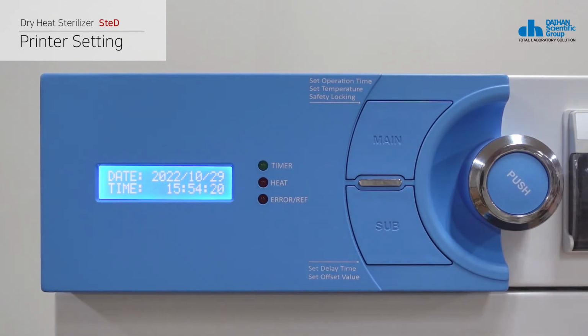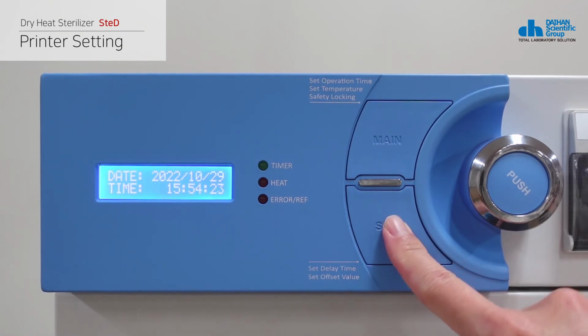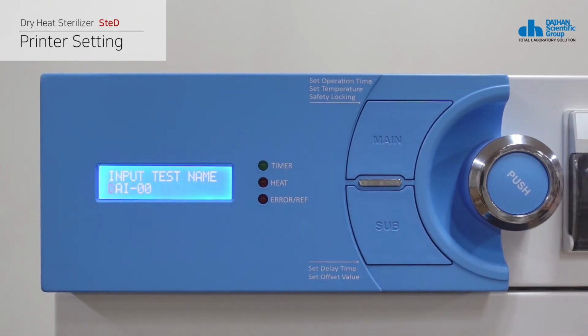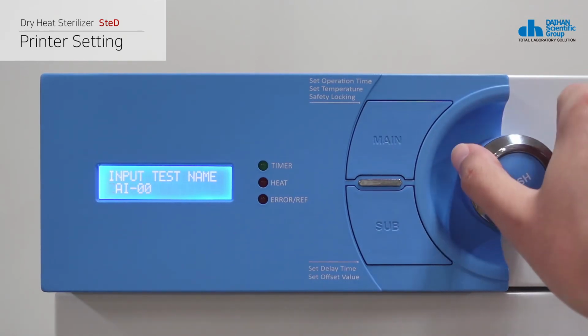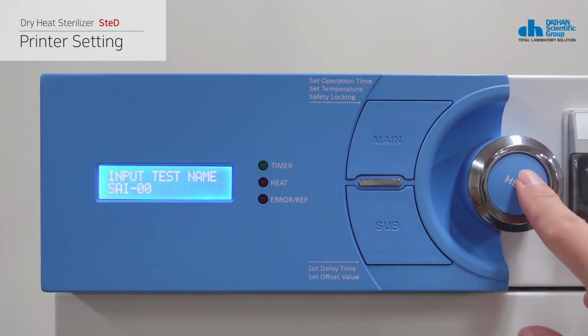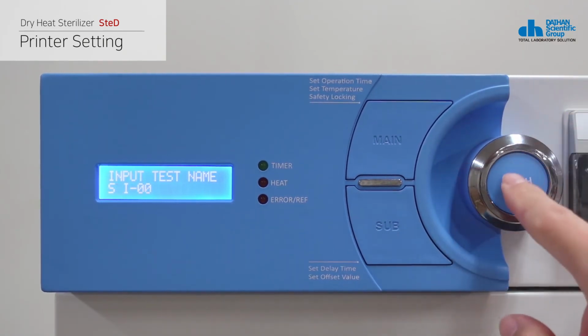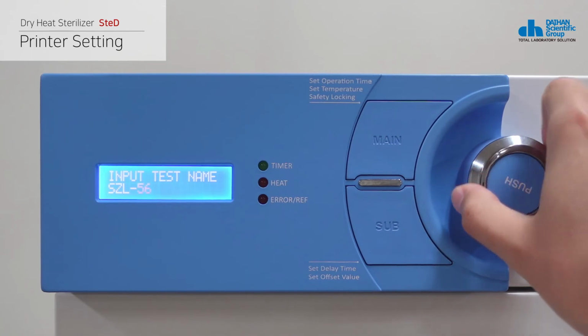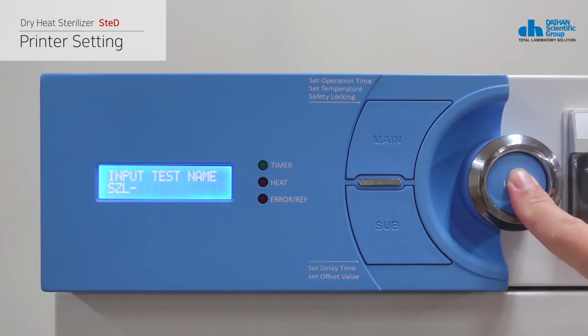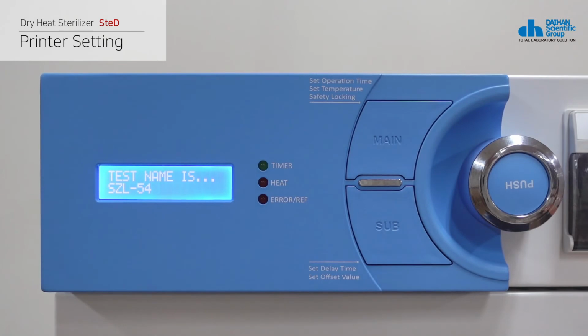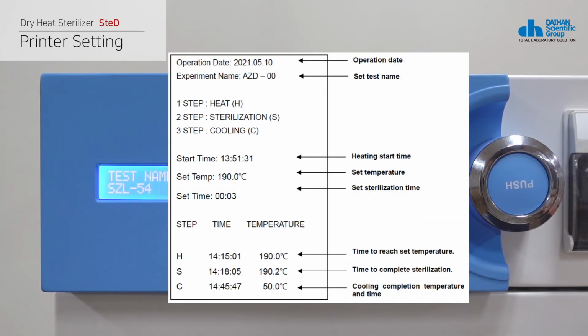Press the sub button on the current time setting screen to switch to the screen where you can set the sterilization test name. Pressing the push button moves the cursor that can be set, and turning the knob sets the value. When you press and hold the push button after the setup is complete, the screen flashes and saves the setup. As sterilization proceeds during product operation, the set date, time, and test name are printed out. The temperature and time information are printed at the end of each sterilization step.